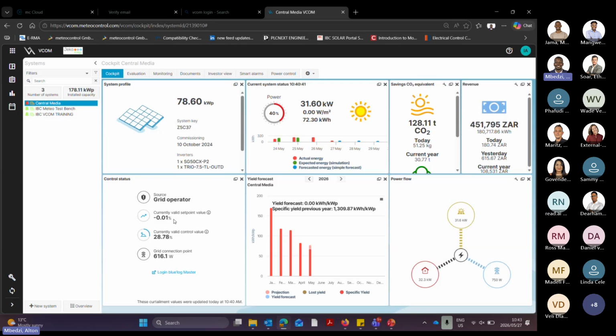So this set point is in relation to the meter. The set point is minus 0.01%, which is this percentage in relation to the technical data you've placed onto your blue log. When we did the whole commissioning during our hands-on training, you'll know that 0.01% is probably zero feed-in. If it's negative, you're trying to take from the grid, and the 0.1% is sort of a buffer. In this case, I'm assuming this is what the client did, but this is basically zero feed-in at the moment.